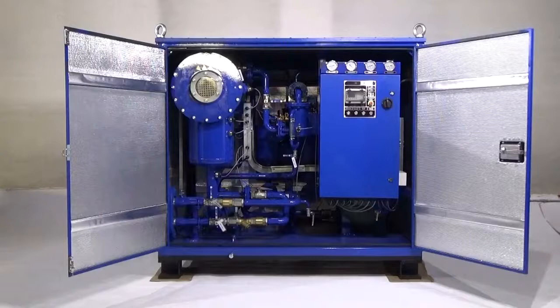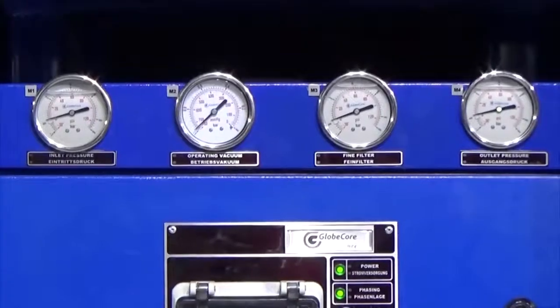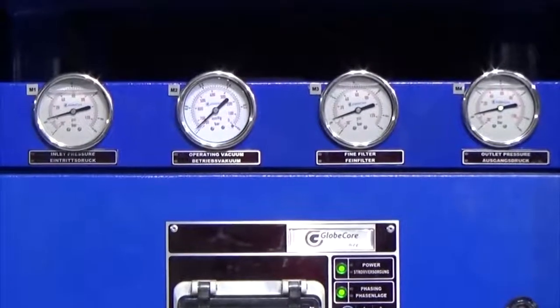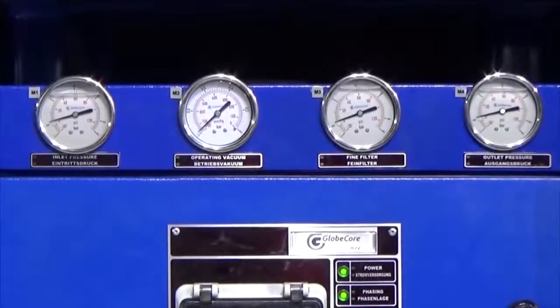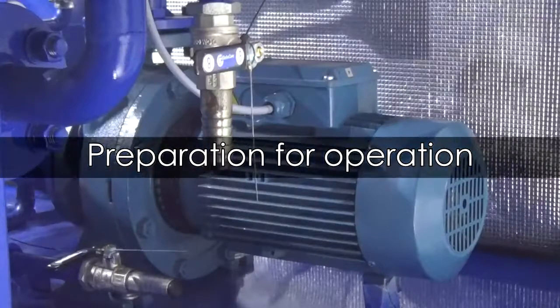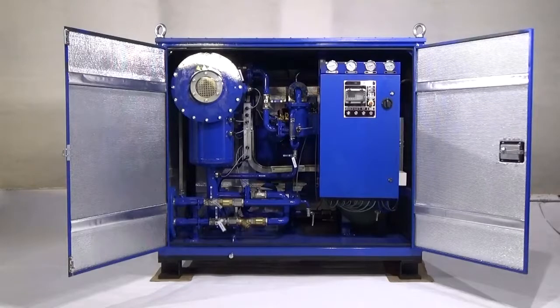3 pressure and vacuum gauges and 1 vacuum meter are installed in the unit for visual control of pressure and vacuum. Preparation for operation. The unit must be sufficiently lit and installed on a flat horizontal surface so as to ensure unobstructed access to the controls. Ground the unit by connecting the grounding device with the unit's grounding bolt with a copper wire. Check that all valves are shut.